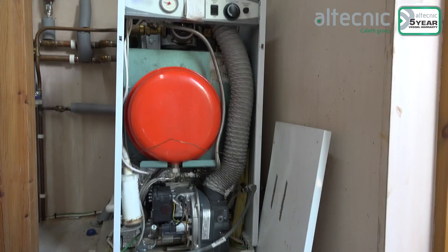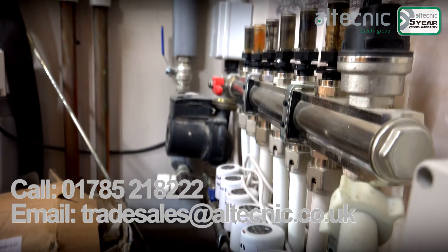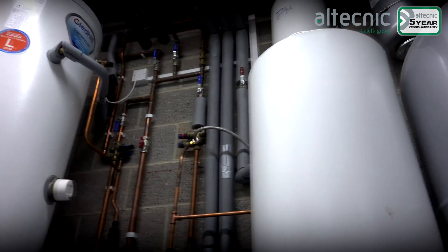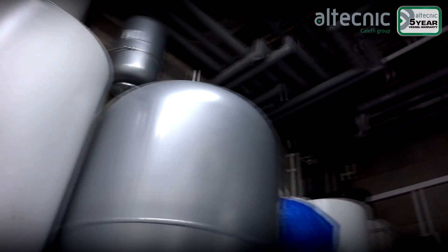It's very difficult to size expansion vessels properly for the system by eye, and we recommend using this handy Altecnic calculator to find out exactly the size of expansion vessel that you need. It's free and you can get it by visiting the website appearing on screen right now. Because this heating system is quite large and has a range of different heating methods — from underfloor heating to a couple of radiators plus three unvented water cylinders — a 25 litre expansion vessel should be adequate for the job.